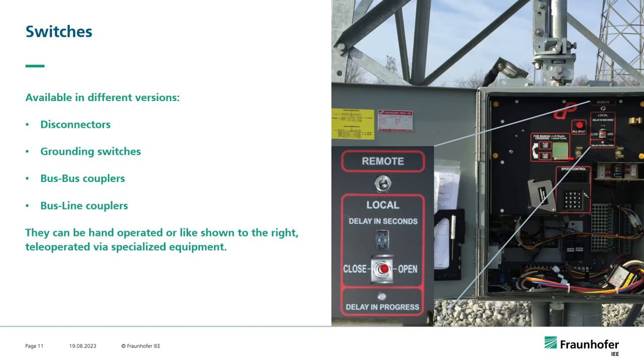This system works so that you can either use it by hand, putting in a hand crank and cranking the switch on your own, or you can toggle a switch and it will switch, or you can send it a command so that when it receives the command, it will open or close. We use these switches to change topologies. For example, you can isolate buses, disconnect stuff, ground buses and so on, which is quite important for getting our power grid to run.